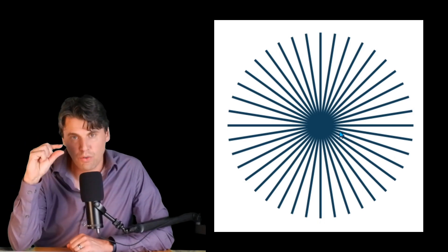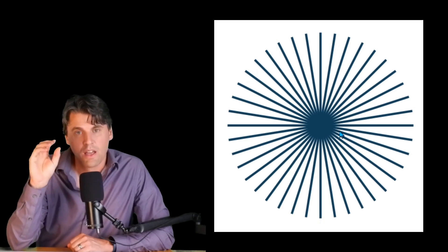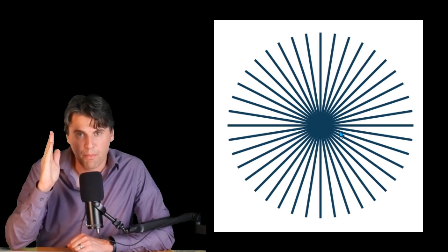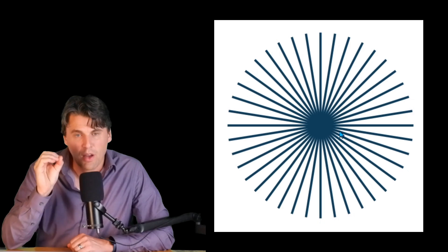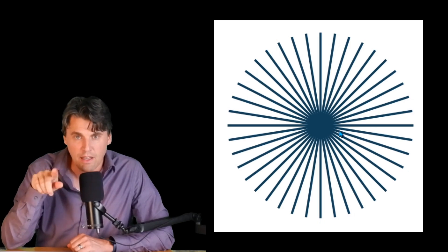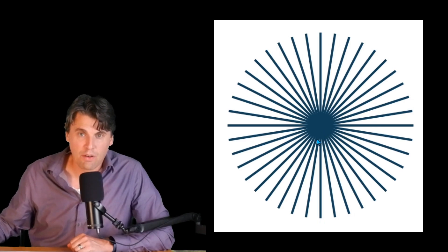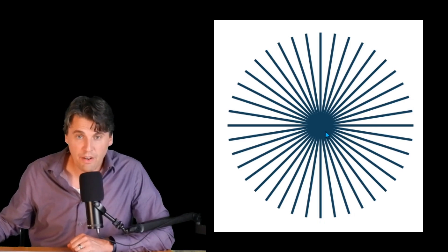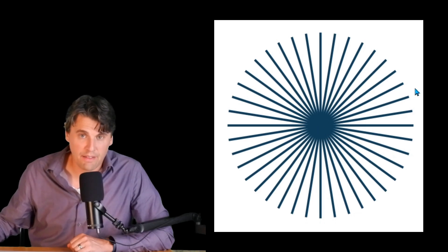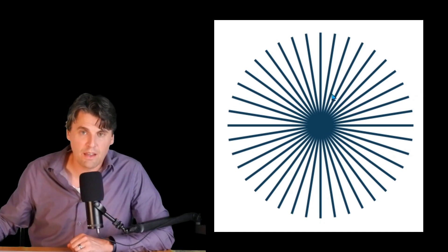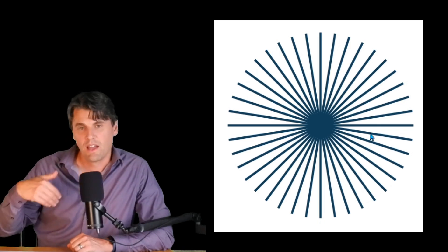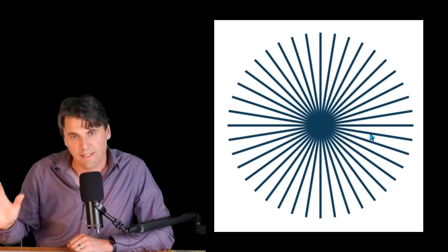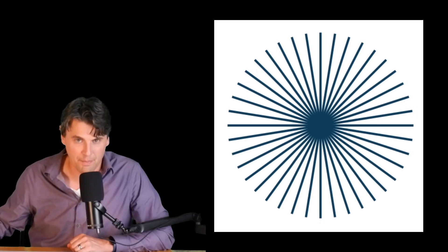that means now the two objects, namely those two spokes that are right next to another, you're going from being able to distinguish them to not being able to distinguish them right at that border there. That's what we would call that limiting spatial resolution. And right in the middle, there's actually going to be gradations or numbers written down on this test pattern that you can see. Once you get to a certain point, this is actually going to be the limiting spatial resolution. And then you would actually document that after you make these measurements on your system.